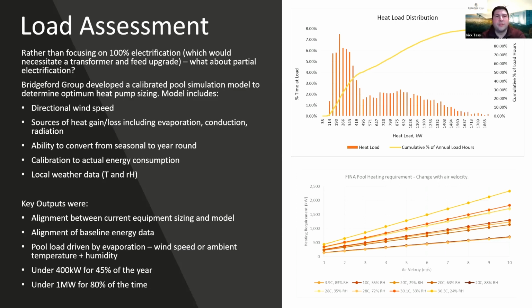Given the pool load was driven by evaporation, wind speed, ambient temperature and humidity, this model produced some interesting results. The heat load distribution shows that 45% of the year the load is under 400 kilowatts, and under a megawatt for 80% of the year. So what we actually looked at was partial electrification to provide the best bang for buck from an emissions reduction opportunity. Next slide, Brendan.